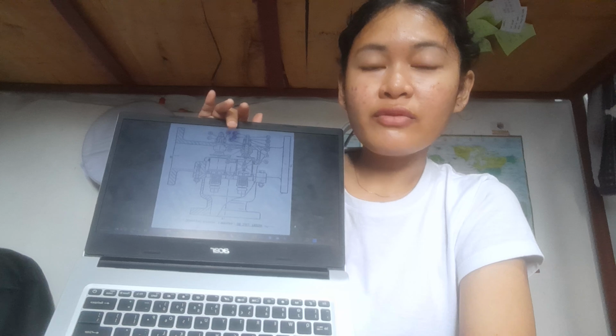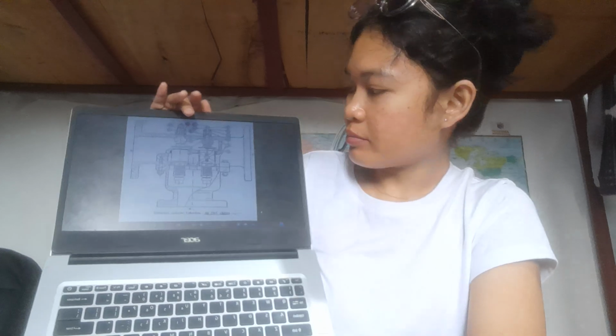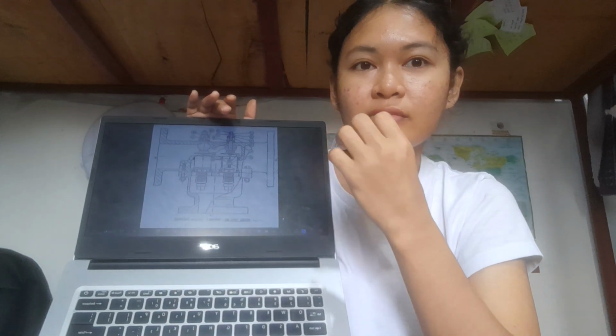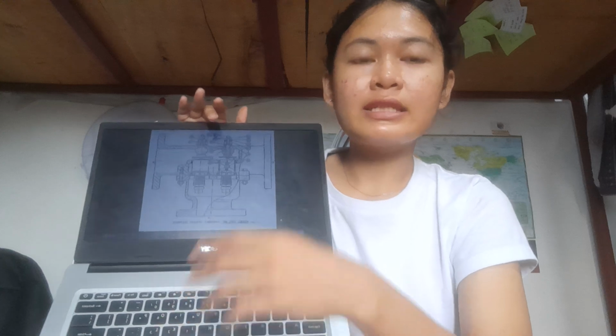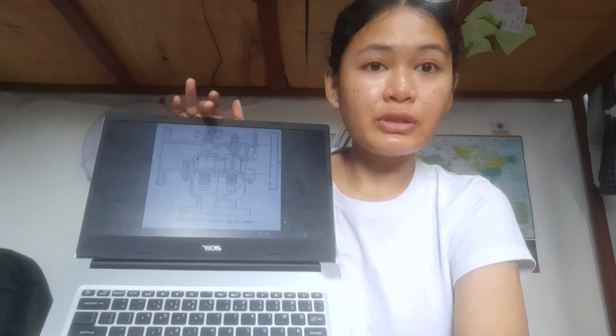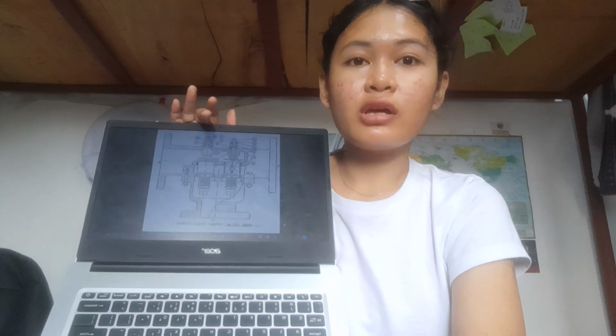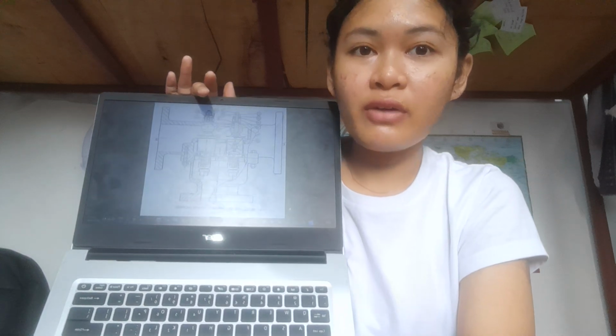Thermostatic element. This is the core of the valve, the sensing valve. It contains a special mixture of hydrocarbon wax and powdered copper. This material is highly sensitive to temperature changes and can be thought of as the heart of the valve.